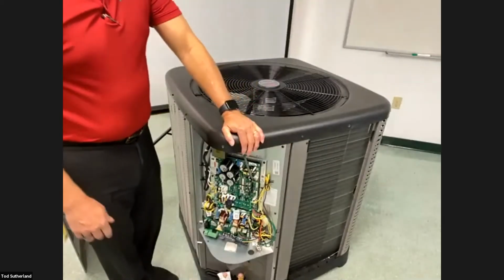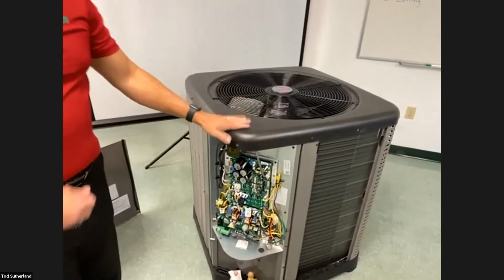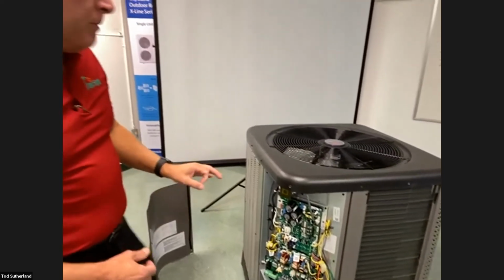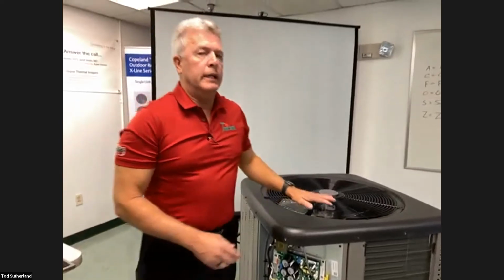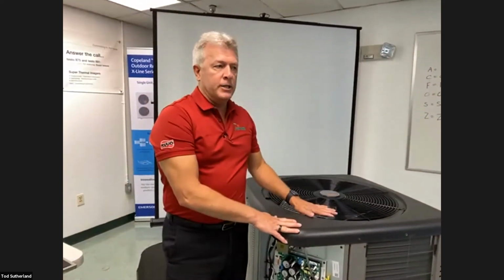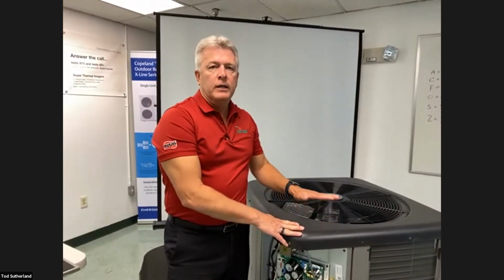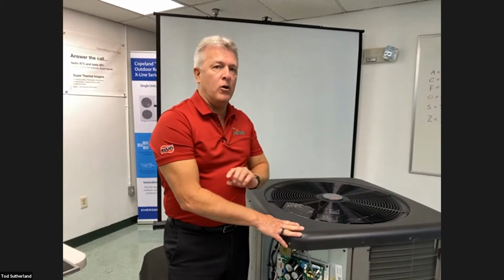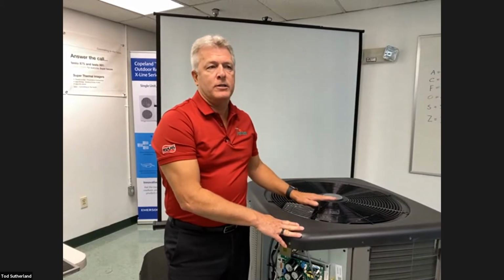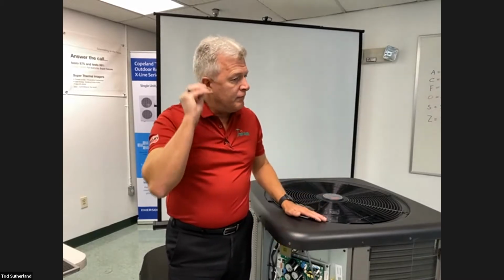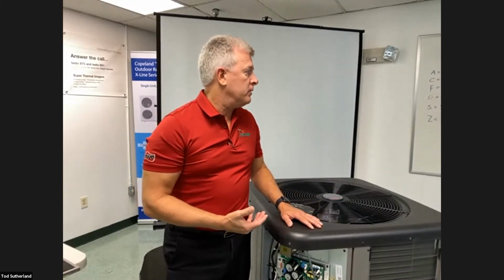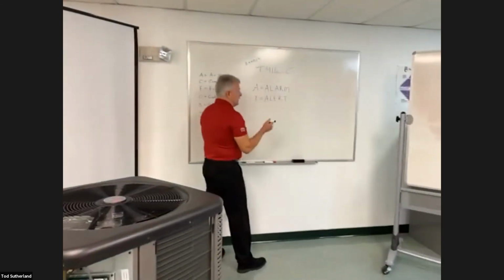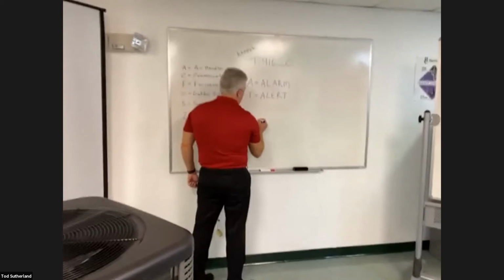From there, on the heat pump models, you're going to have stepper motors that go to the electronic expansion valves. The nice thing about the electronic expansion valves is that it's the same valve on all the condensing units, and it's the same valve in all the air handlers. So it's a very simple valve. For those of you that aren't familiar, let's move over here real quick. For those of you that aren't familiar with an electronic expansion valve, it's really quite simple.